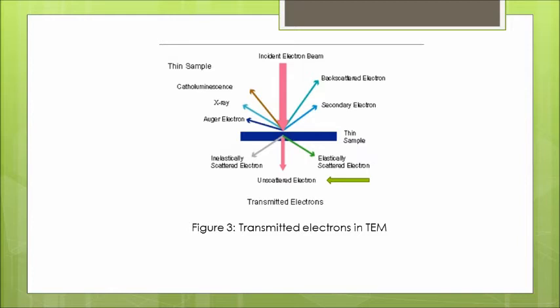The second one, the elastically scattered electrons are useful to obtain diffraction pattern of the sample in the selected area electron diffraction mode. And finally, inelastically scattered electrons are characteristics of the sample elements and hence are useful for extracting information of a specimen region.